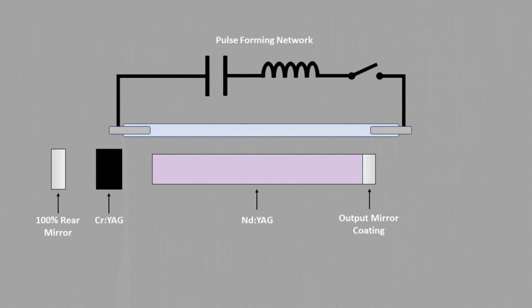The speed of the discharge needs to be closely matched to the specifications of the flash lamp and the fluorescence lifetime of the laser. In this case, it's about 200 microseconds, which is well matched to the neodymium YAG's 230 microsecond fluorescence lifetime. For simplicity, a switch is shown in this diagram. In reality, the lamp will be triggered by means of a high voltage trigger circuit.